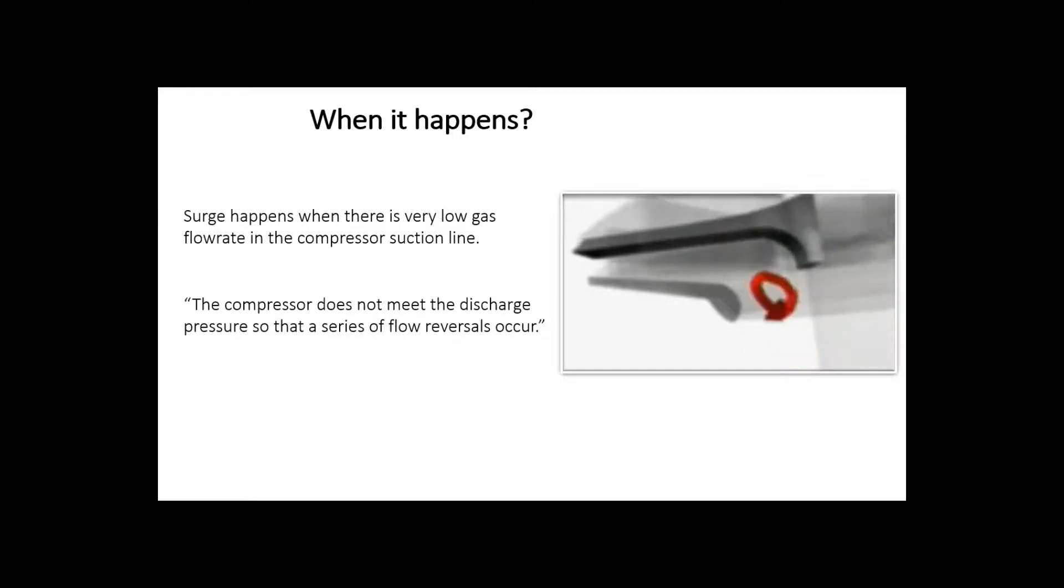The reason behind these flow reversals is that the pressure in the discharge piping section is higher than the pressure in the compressor section, and the compressor performance does not meet the discharge requirements.